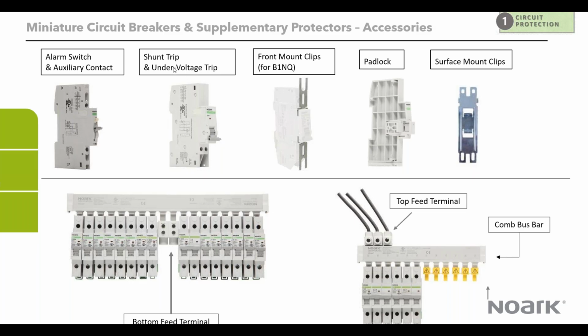The shunt and the undervoltage are examples of accessories. You typically want to use a shunt when you're trying to remotely open the breaker. And an undervoltage is just a way of protecting the breaker from an undervoltage situation. So if you have an undervoltage situation, it prevents the breaker from closing.